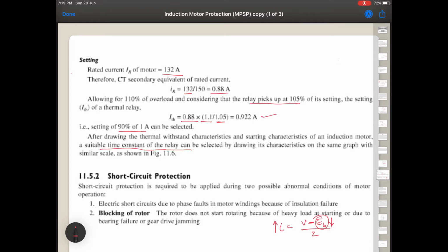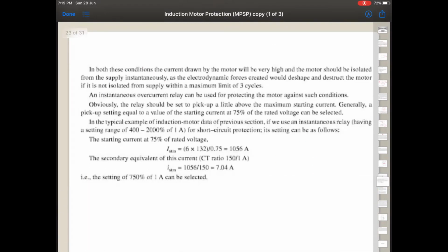It may occur during starting, which is why at the starting of the induction motor it draws high current, and the other cause is electric short circuit. And electric short circuit happens because of insulation failure. If the motor is persistently overloaded, then it may heat up, insulation failure may happen, and a short circuit can occur.